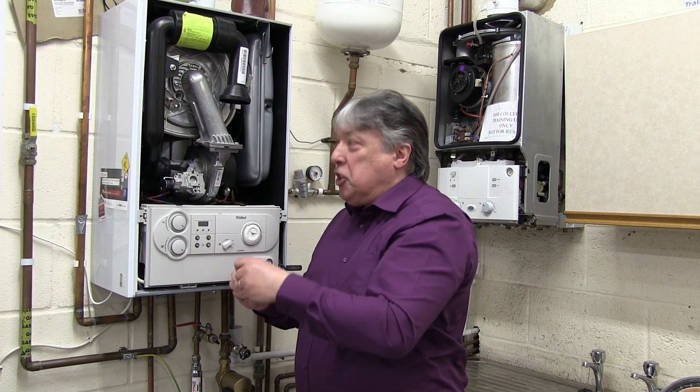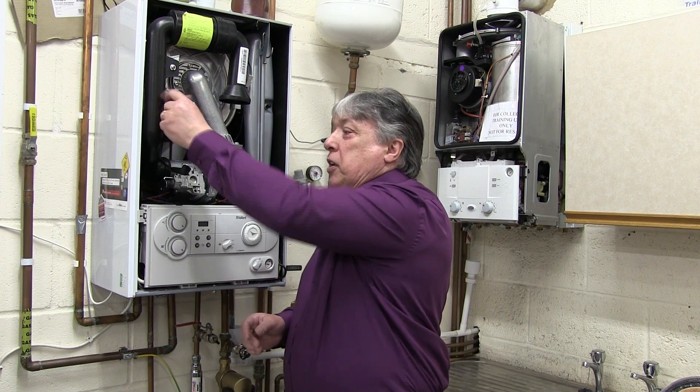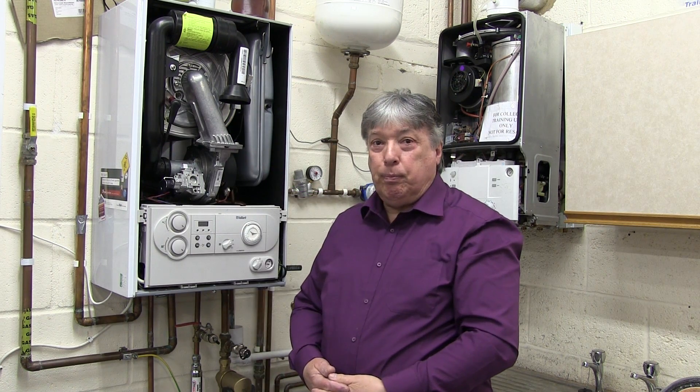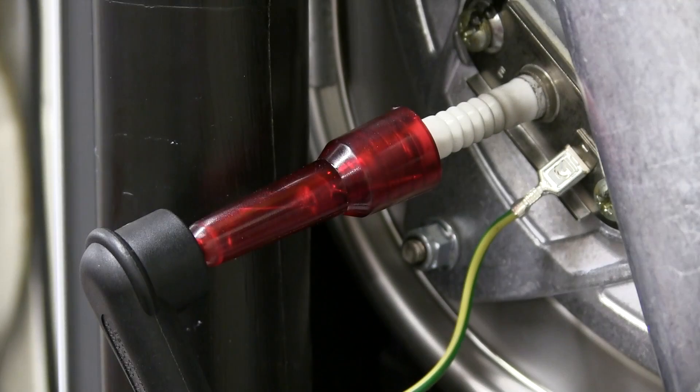We remove the HT cable, put it in the tester and plug in. I've installed the spark plug tester in line. Normally I always test in the central heating mode, but in this particular situation I'm going to turn on the hot tap because it's much faster.